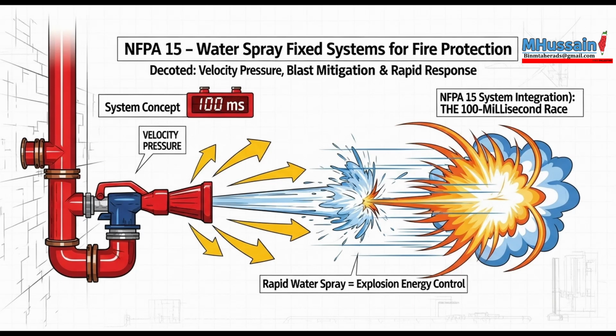Also, piping 12 inches or larger needs to be the welded flange type. This resists separation under blast shock much better than threaded or grooved joints. And Annex 8.6.3.6 advises engineers to physically shield the piping whenever possible. Route it behind structural steel, use existing columns as barriers. Using the building itself as a shield against shrapnel or pressure waves. Exactly. Protect that water delivery network at all costs.